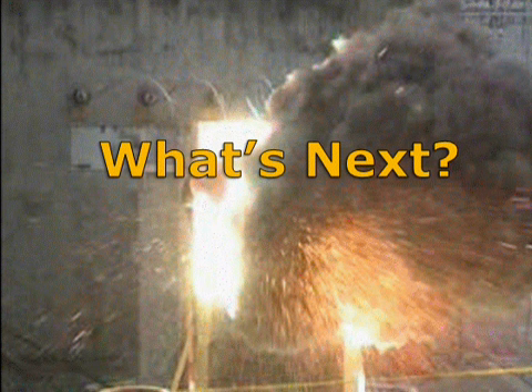So there is an effort. The working members and the chair have been identified, and they expect to create the draft version, get it voted upon, and get it released over the next 2 years. At the end of that period, for the majority of electrical distribution equipment, there will be a guideline that tells you how to test that equipment so that you can certify it as being arc resistant. So it's going to greatly expand the scope of arc-resistant equipment offerings.